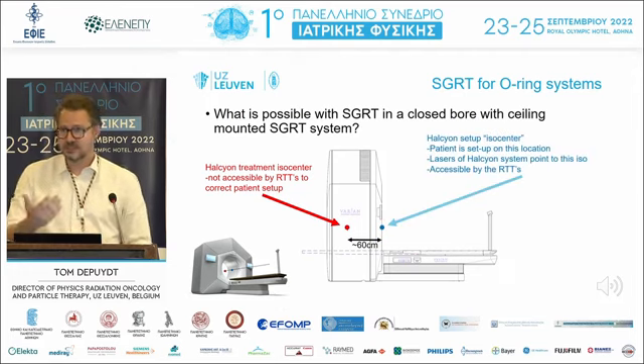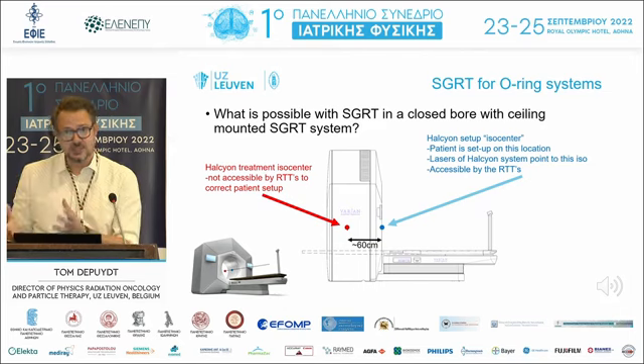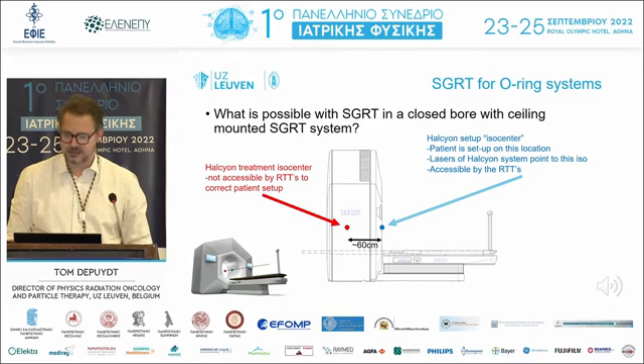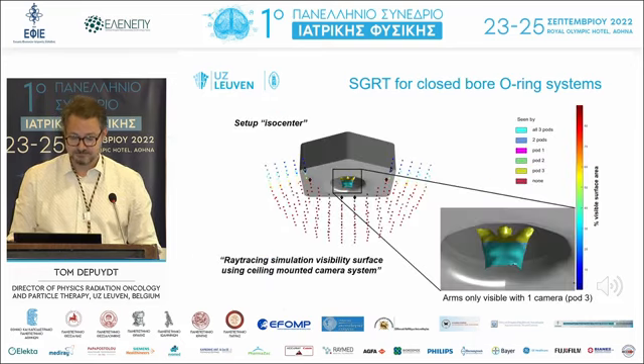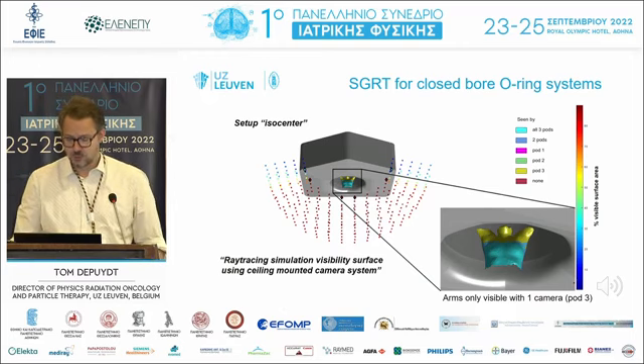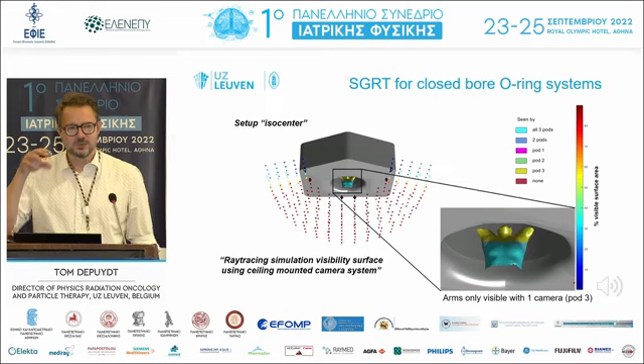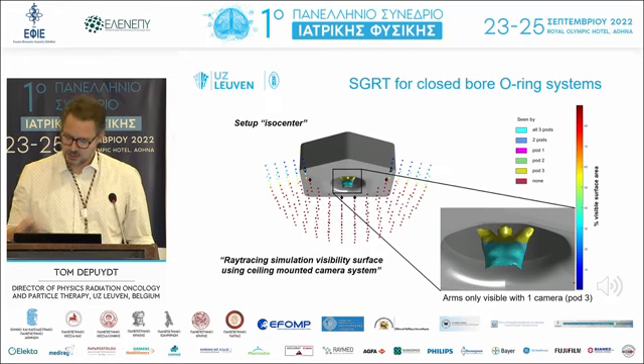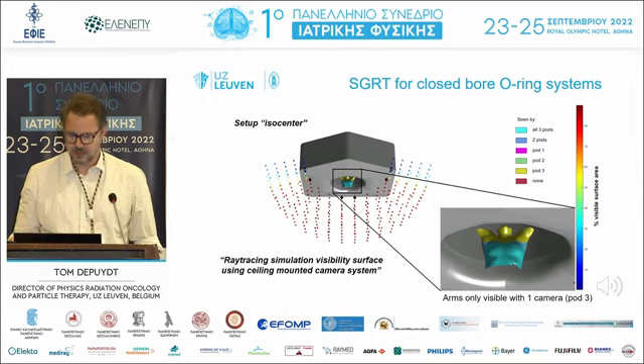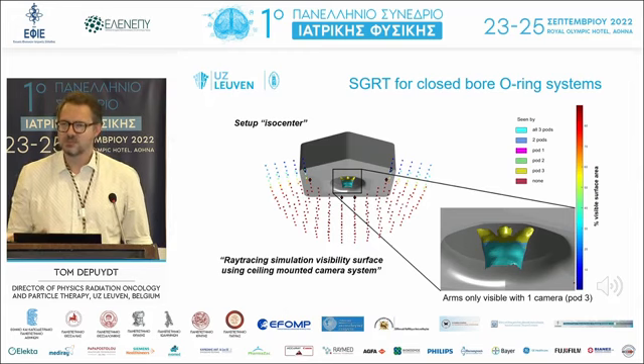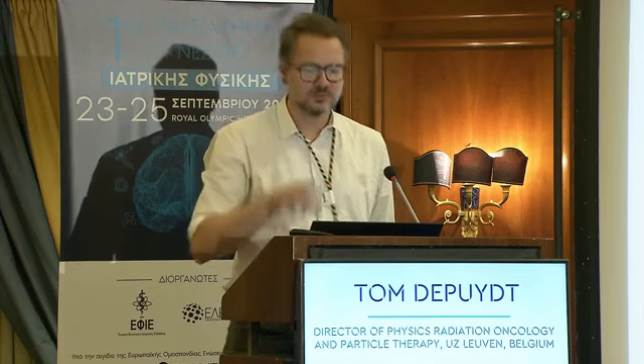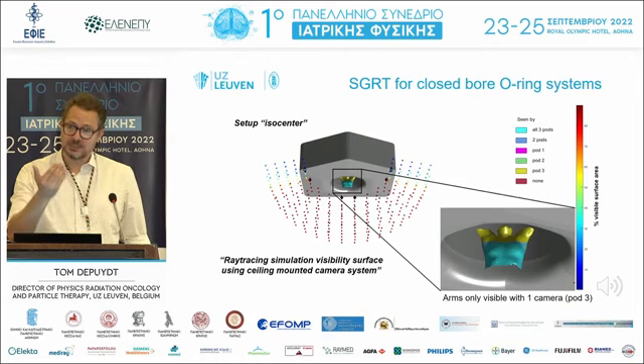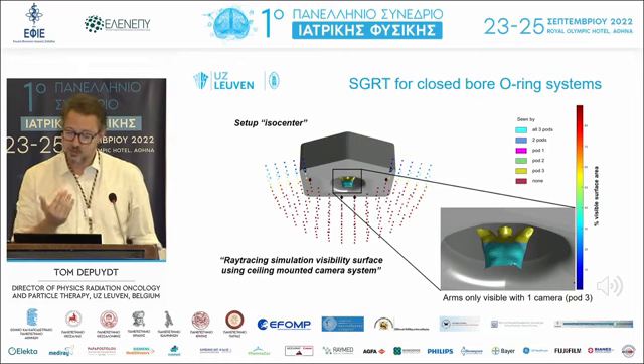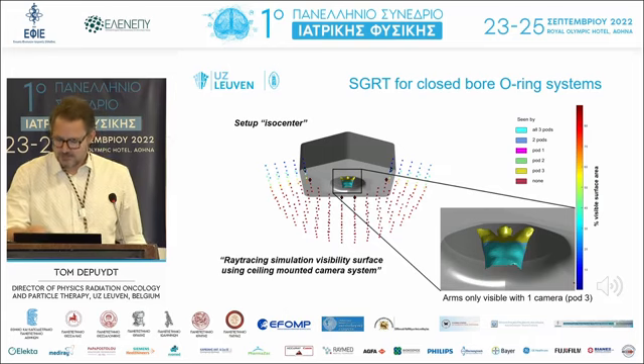You have another isocenter, the setup isocenter, which is about 60 centimeters in front of the system, or at least in front of the actual isocenter. And there you do the setup of the patient and then move the patient inside the system. And there you have access to the patient to change the position if needed. So what we did in Leuven is to investigate whether we could see the patient with the cameras. So we developed a ray tracing algorithm that could anticipate or predict the coverage of these surface scanning cameras. And what you see here is that for the setup isocenter, so that's the 60 centimeters out of the bore, you have quite good coverage for this breast patient.